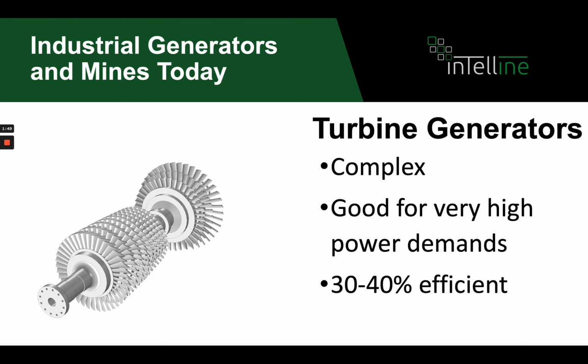Now, despite having one main moving part, turbine generators are substantially more complex in design and require specialized training to properly maintain. The higher tolerances, specialized materials, and unique parts in turbine engines make maintenance more difficult. The turbine engines are efficient and compact power solutions, especially for power demands in many tens of megawatts. In combined cycle power plants, turbine generators can achieve excellent efficiencies of over 60%, but in standalone use, efficiencies are still only 30 to 40%. Load matching is also still quite limited.